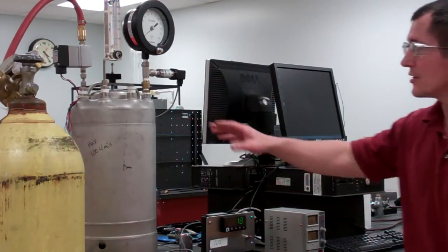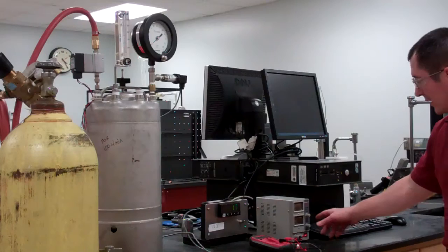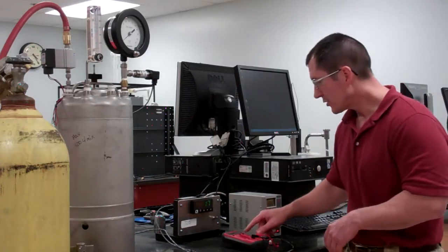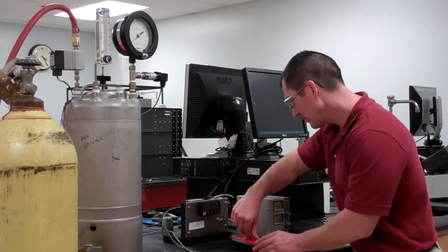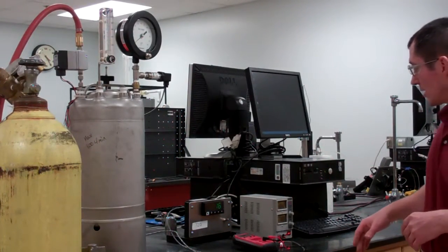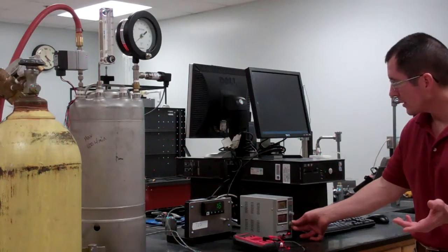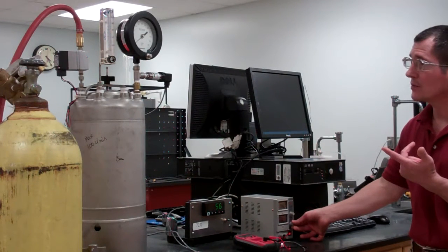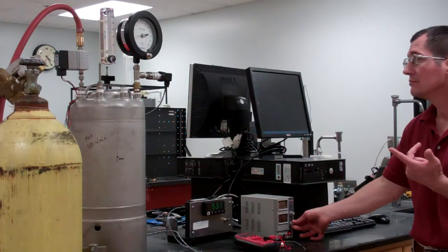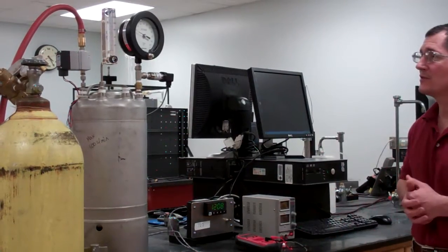And to apply power to the final control element, we're going to turn on a variable DC power supply. And the current should be set to maximum, the voltage should be set to 0, just like it is there. And to read the signal going into the final control element, we'll use a multimeter. And when you come in for recording, you'll get to see what all this is reading. And so I'm going to go ahead and apply some power to the final control element. And as I do, you can see the pressure starting to change. And let's say we want our set point at 15 psi.